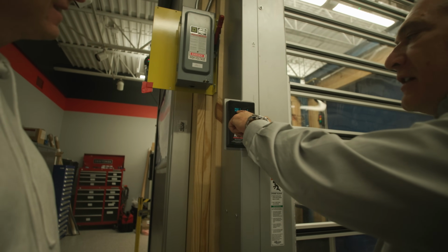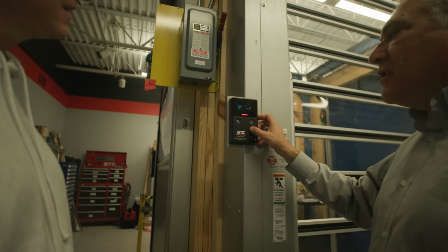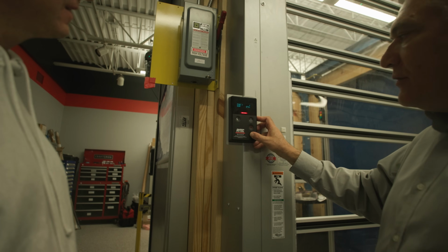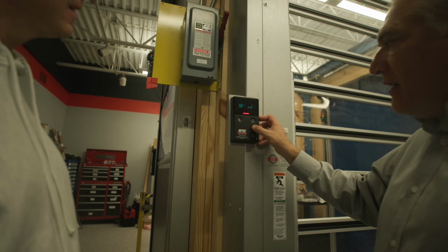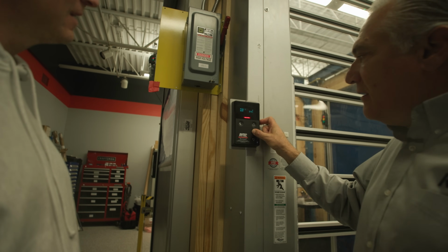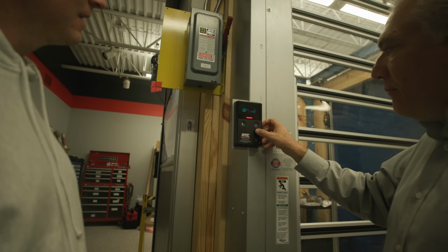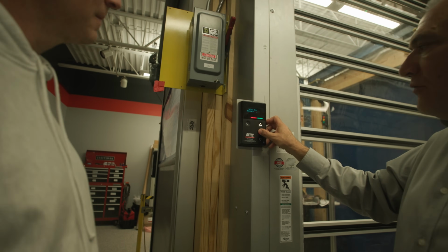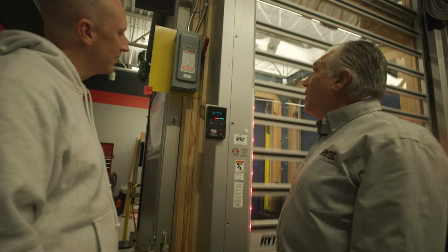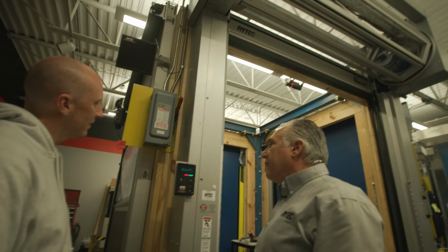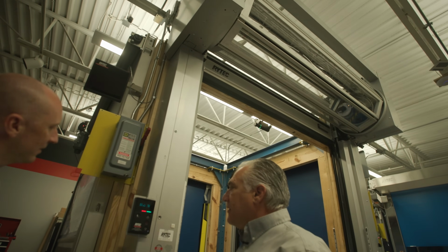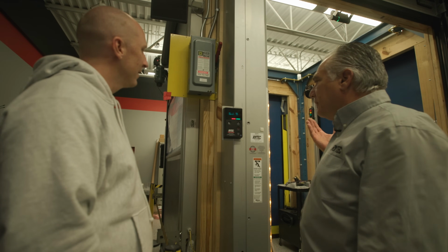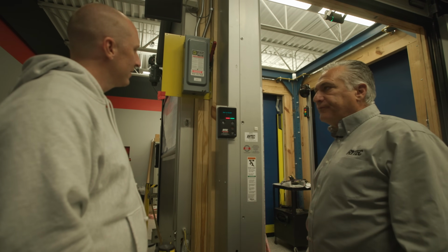The parameter, in this particular case for that timer, is 010. I move it over to the value and use the arrows to adjust it. I'm going to set it to 5 seconds. I'm going to save it till the check mark shows up, and then I'm going to exit. The next time I open the door, it will only count down for 5 seconds rather than 10. You can see it started at 5, and it'll get down to the pre-warning, and then the door will close.